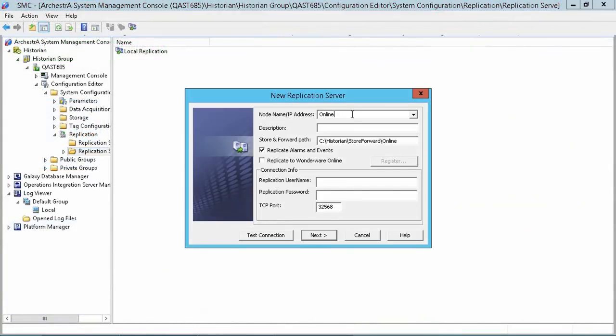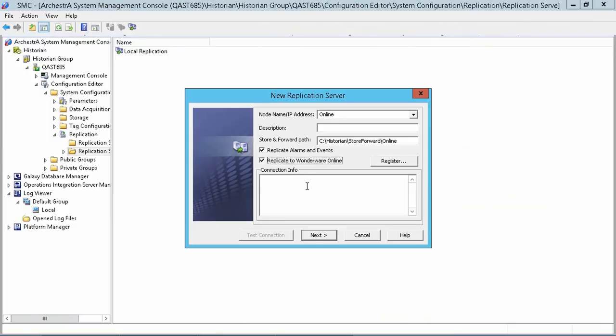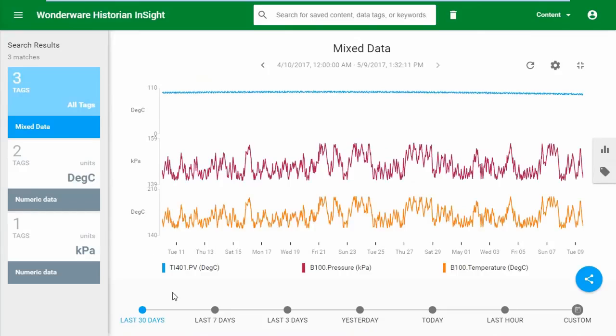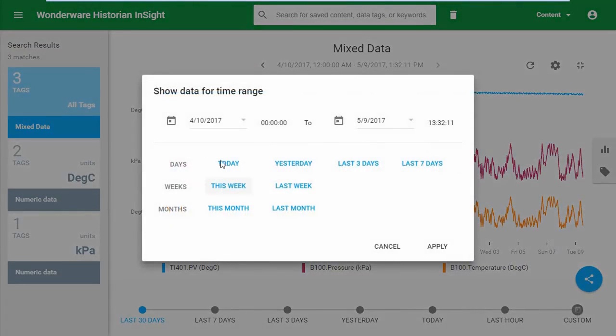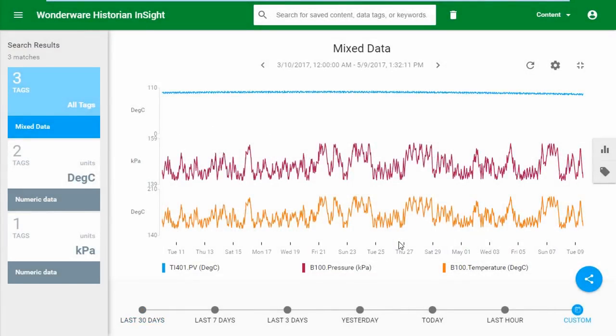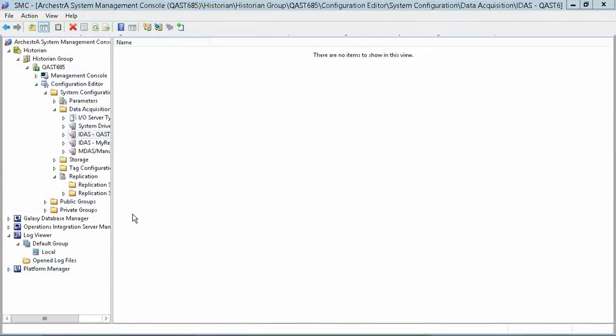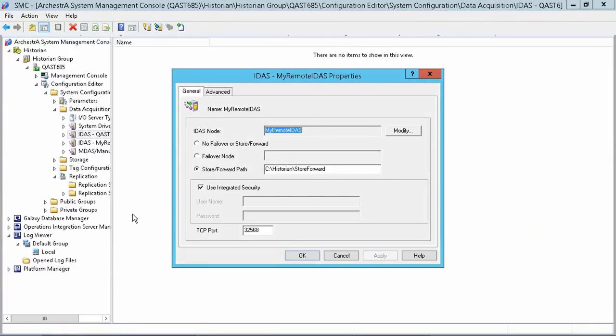We've expanded tiered Historians to also support replicating events to a central system, including to Wonderware Online. Whether you're running reports, using Historian Client Trend, or Insight, or making long-term queries lightning fast, Historian will start optimizing your historical data from the time you upgrade. Look for a separate utility to also optimize your older data to be available soon. Finally, if you're using a remote IDAS for reliable data collection, look for significant improvements over slow and intermittent networks, including much lower bandwidth requirements.